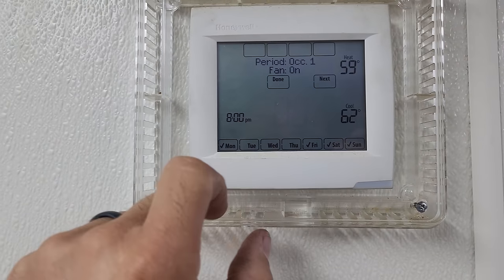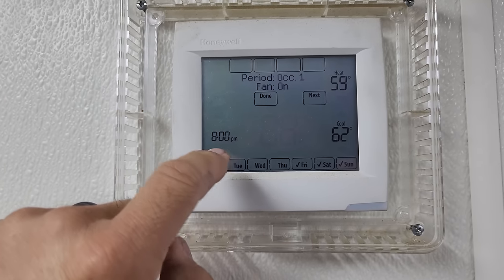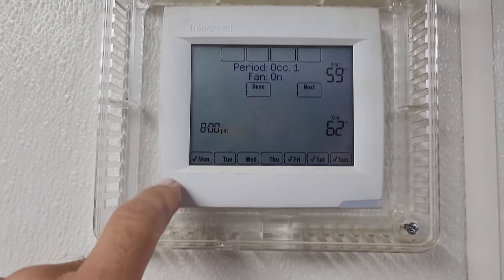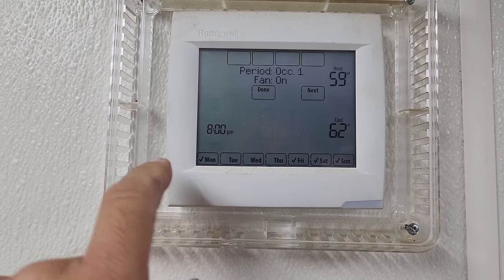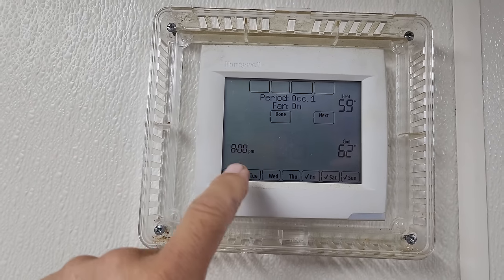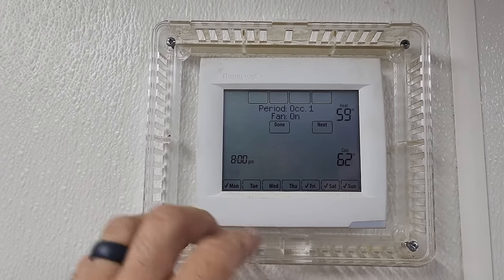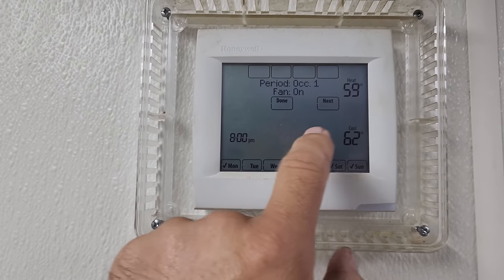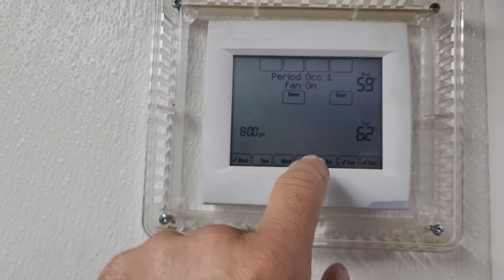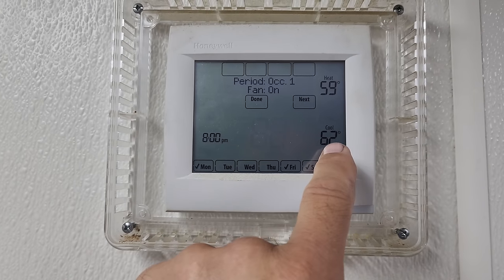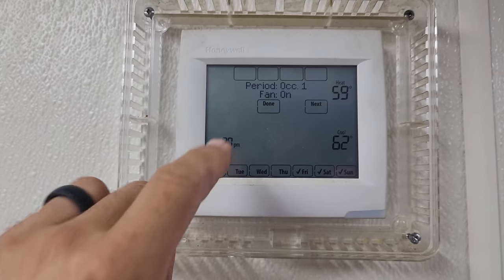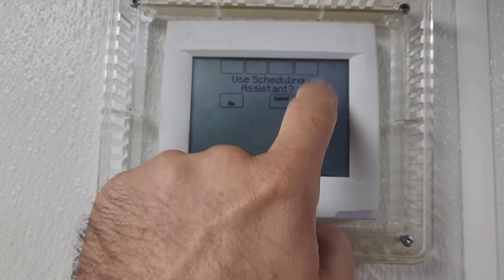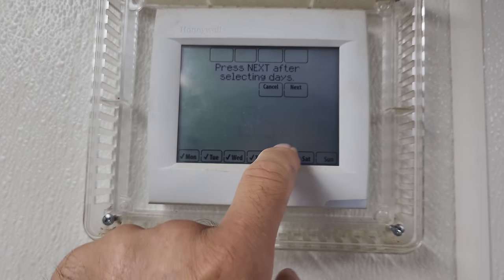Going through the service call for the kitchen AC not working, I found that the thermostat is programmed incorrectly. I'm not going to assume that's the only problem. More than likely the AC wasn't working and someone came in thinking they were going to fix it by playing with the thermostat. This one is set to turn the system on at 8 p.m. and turn it off at 1 p.m., with cooling set to 62 at 8 p.m. It's all messed up, so I'm going to go back in here and change the whole schedule the way I want it — select every day, make it the same.